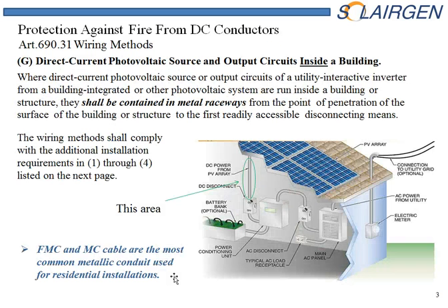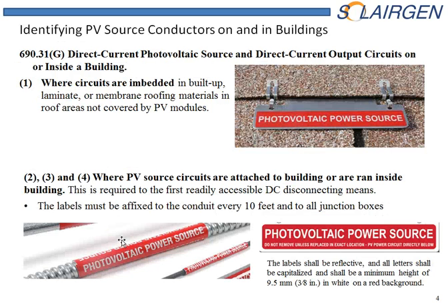Whenever we run our circuits, our source circuits, into buildings, we must have them in metal conduit. If we're on the building, we don't necessarily have to have it in metal conduit, but it should be. We see a lot of PVC conduit run on the surface of buildings. The bad thing about PVC is that it will sag over the years in heat. But whether you do metal on the outside or PVC on the outside, they all require identifying.